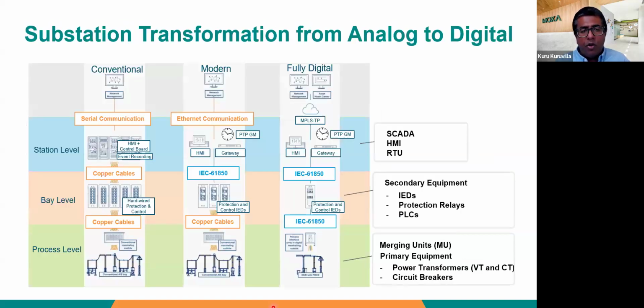So now, if you look at how the evolution of grid substation automation has happened. On the left side, you can see the traditional, pre-automation type substations, where you have the physical devices at the process level connected by control cables. And then you typically have serial communication going from the protection relays to the central level. What then happened in that evolution is the communication from the bay level, so from the relays up to the SCADA system, got transformed into digital Ethernet communication, for example using 61850. But the communication from the device level to the IEDs still remained in the analog world, if you will.